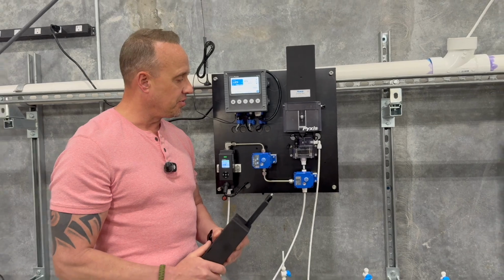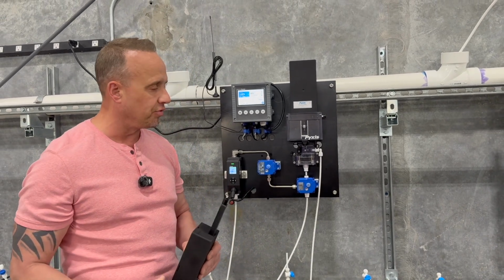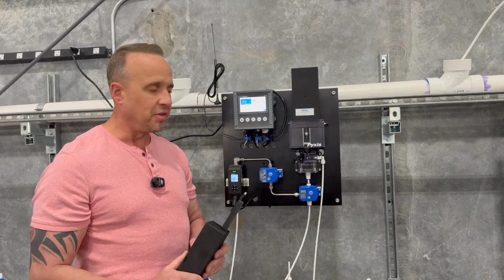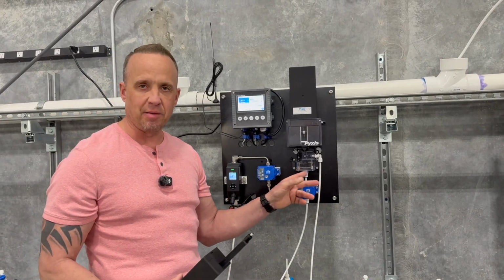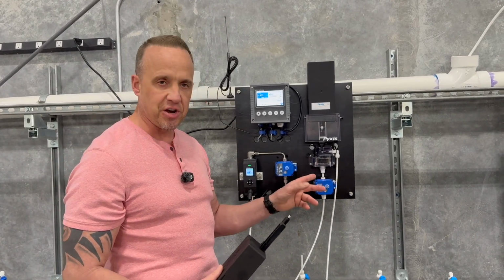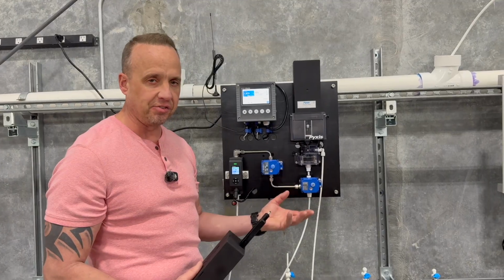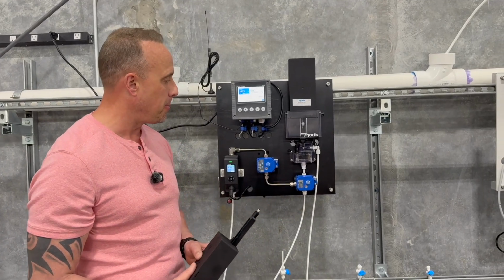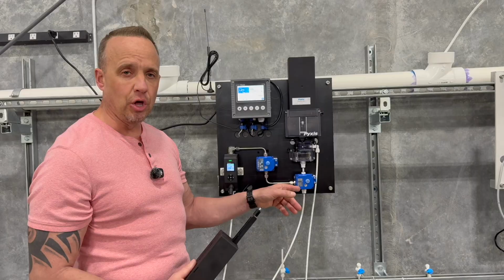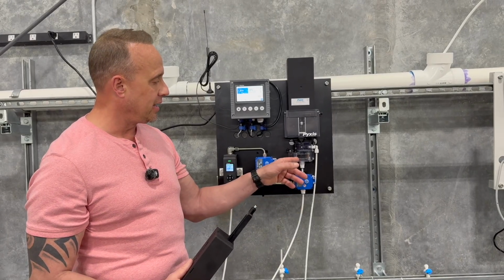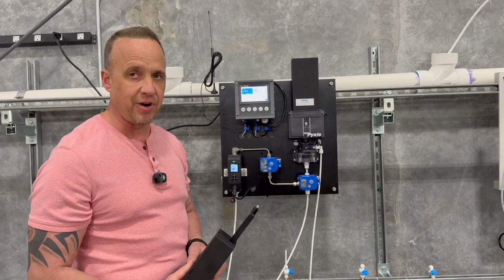An indication or a scenario of that might be if the analyzer was, let's say, 300 to 400 feet away from the sample point, we would want ample flush time of that reaction chamber to give a freshwater sample before the reagent is administered into conducting the sample. After the flush occurs, the 3-way valve closes and you now have a completely primed and full reaction chamber with fresh sample.